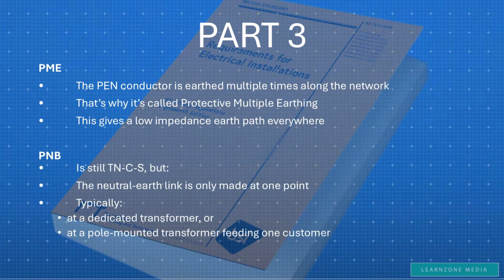PNB, the new thing in the regulations, is still TNCS, but the neutral earth link is only made at one point, very close to the installation, typically at a dedicated transformer or a pole-mounted transformer feeding one customer. So instead of multiple earthing points, we will have a single earthing point near the customer. This is not a new earthing arrangement as such, it's just formal recognition of something that's been in use for many years.